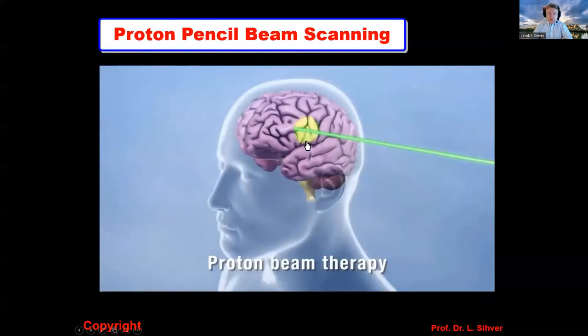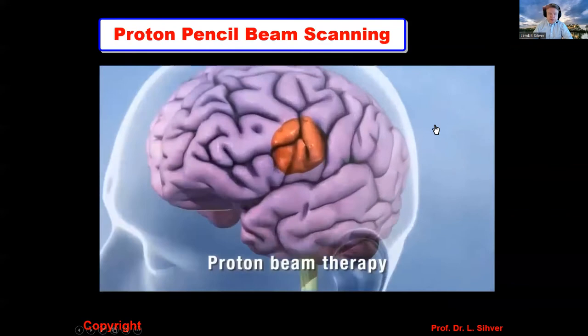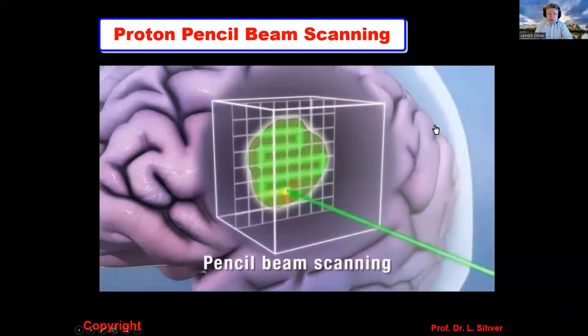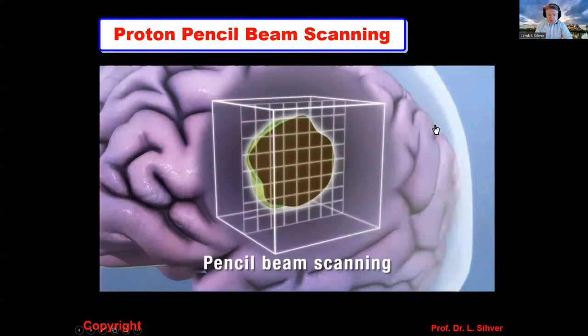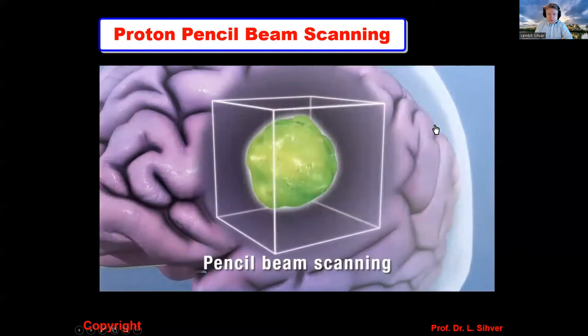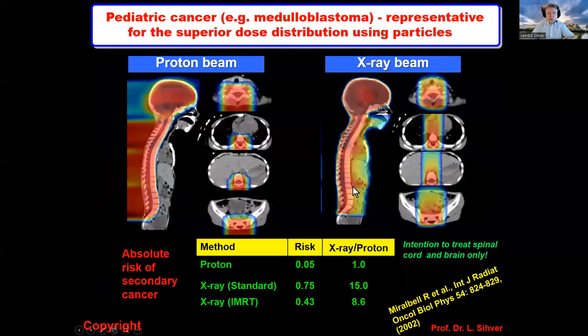If you look at proton therapy, one uses proton pencil beam scanning. That means one basically paints the tumor three-dimensionally by changing the energy of the protons and changing the direction of the magnets of the beam. And then you have this three-dimensional pattern. Previously, one used a passive system with range scatterers, range filters, bolus, etc. Some facilities still use this, but if you have extra material in the beam line, you will cause more projectile fragmentation of the beam, and you will cause target fragmentation, and you can get neutrons, and you can get more dose to the healthy tissue, so you get more normal tissue complications.